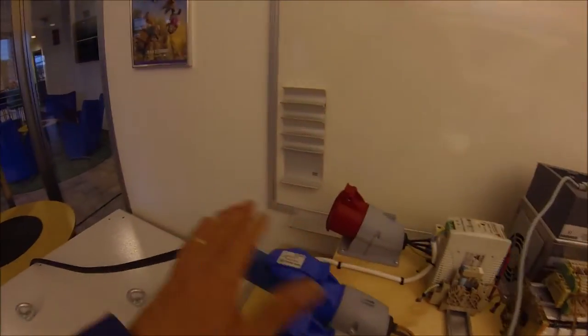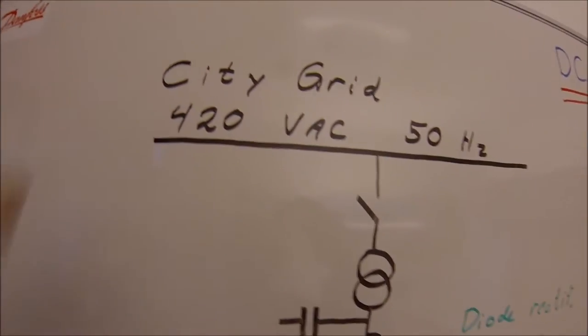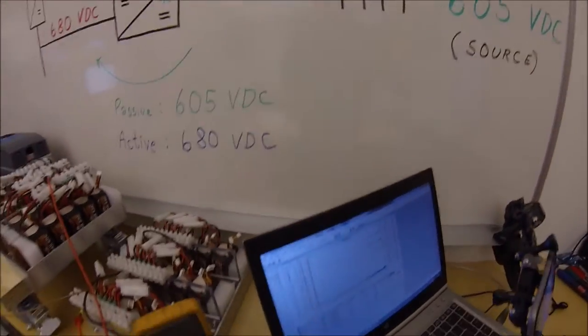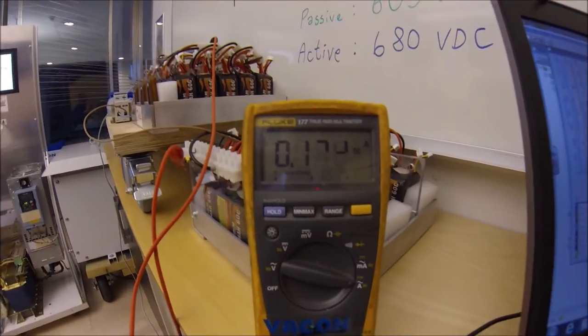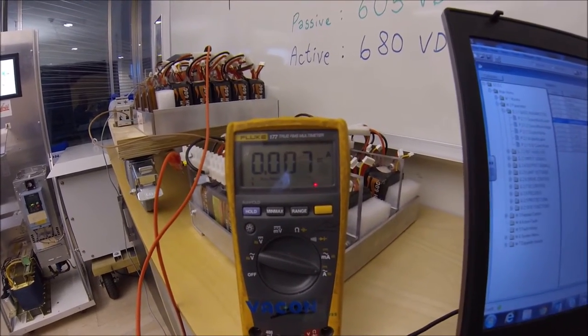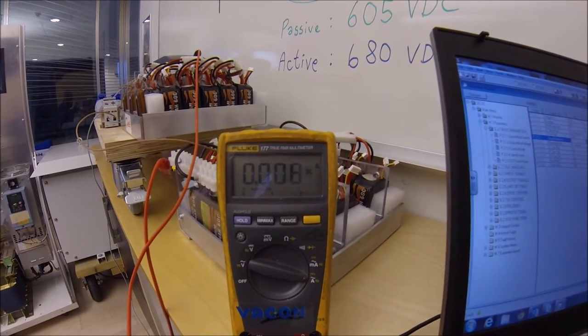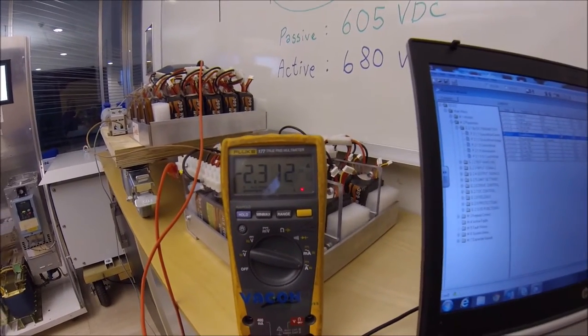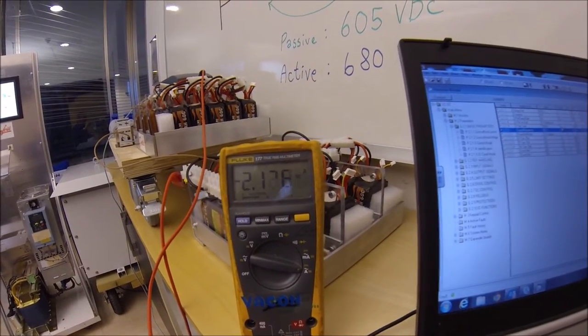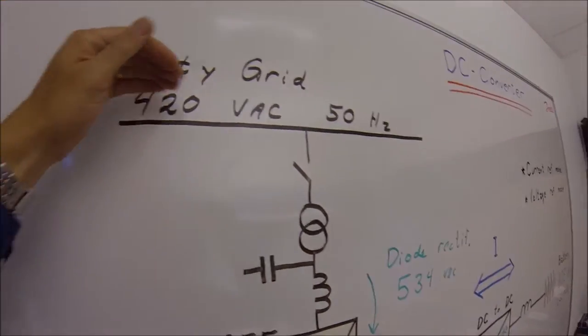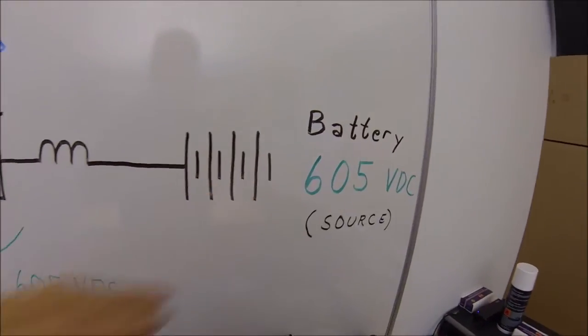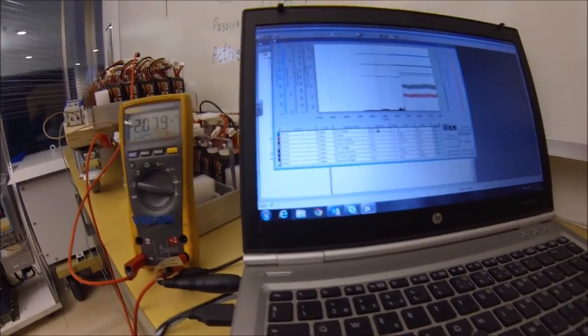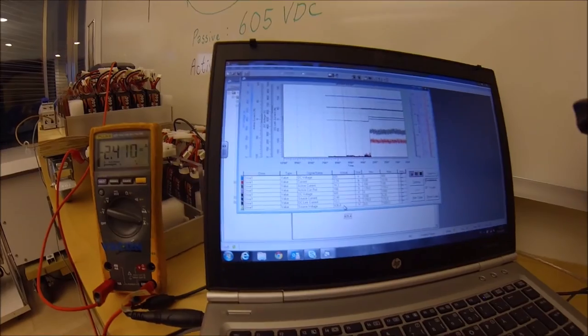Now that we have an active front end connected to the city, we can actually transfer energy to the city. So let's try to give a current reference to the DC converter. Here we can see the amperes going right now. The current reference, we could put it to some, let's say, 50%. Now we see 2.3 amperes about. So the energy is now flowing from the city through the active front end through the common DC bus to the battery. And we see that the DC converter actually has raised the DC voltage quite a bit to 635 to push this current into the battery.